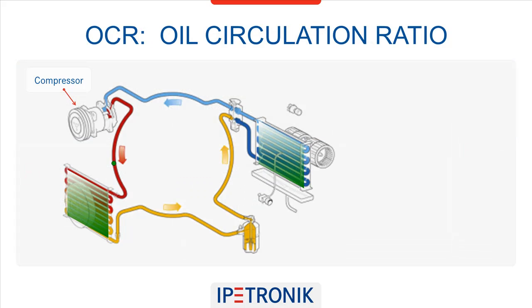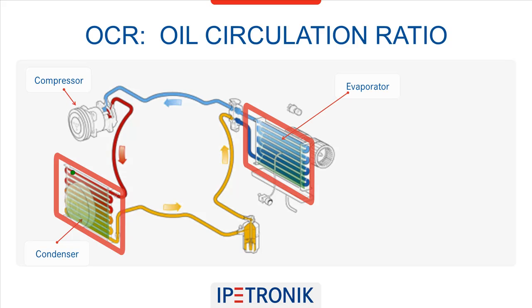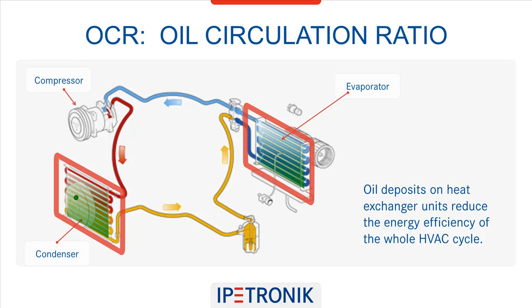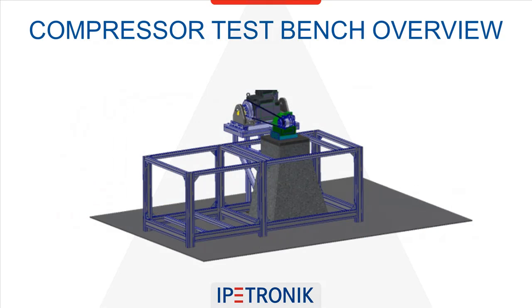The oil flow inside the HVAC system is, from a technical point, absolutely necessary as it delivers the lubrication required for compressor operation. As the simulation indicates, increasing oil circulation volumes lead to oil deposits within the pipework, the heat exchanger condenser, and evaporator. Resulting oil deposits can reduce the heat exchange performance of the condenser and evaporator due to isolation effects. Because of this, a vital aim of compressor manufacturers is to reduce the oil circulation flow to a minimum. Now we will present an overview of the main modules of the test bench.